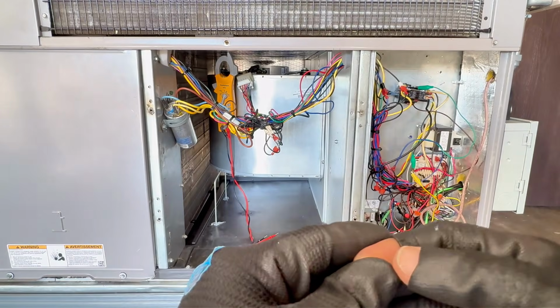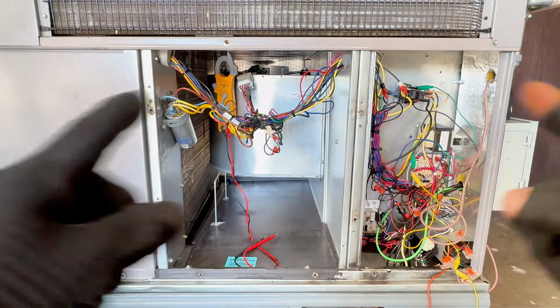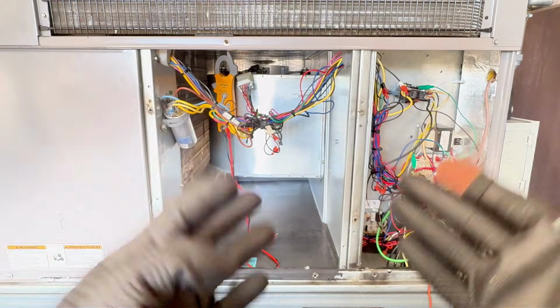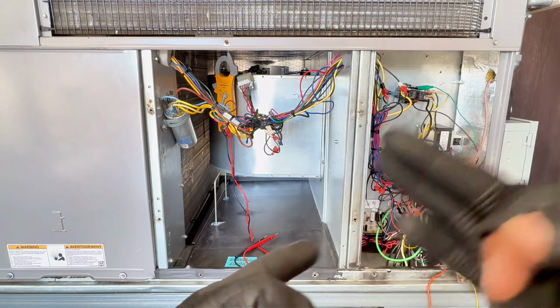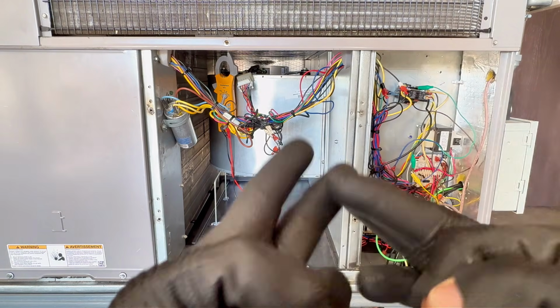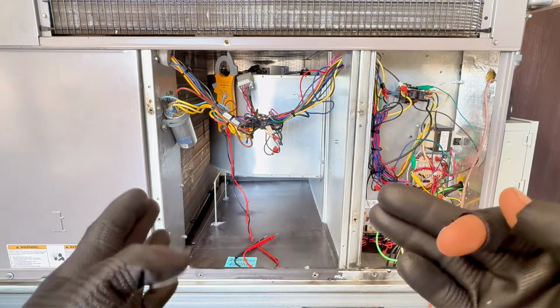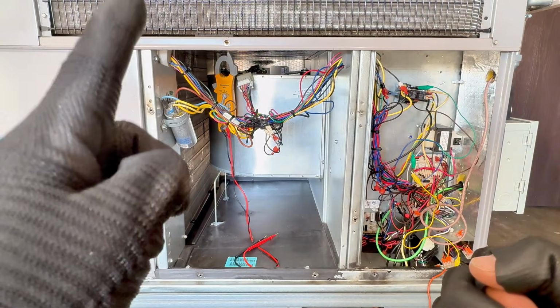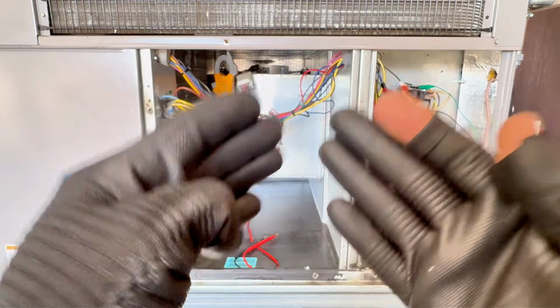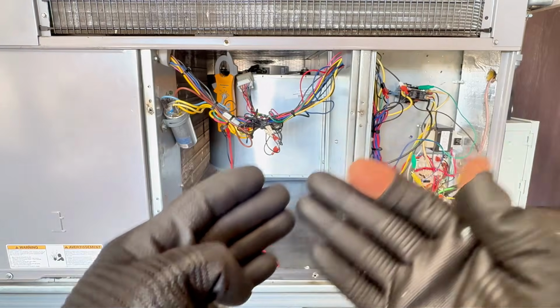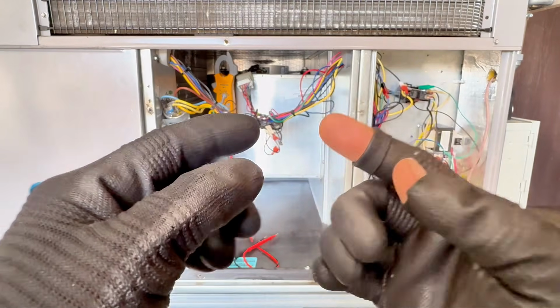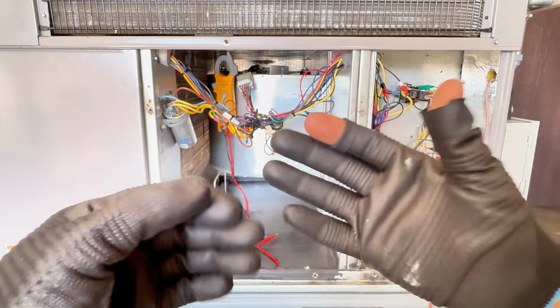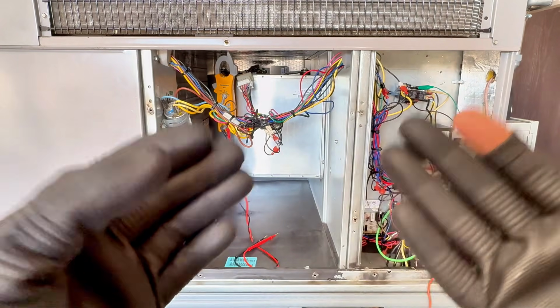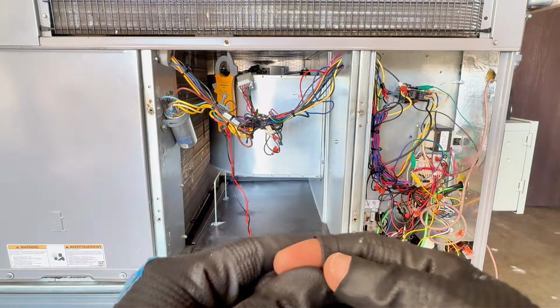So let's say you go on a service call and you're calling for cooling. In this specific package unit, this is a heat pump. So we're sending 24 volts to the contactor coil and the reversing valve. And sure enough, the compressor turns on, your condenser fan turns on, but you notice that your ECM, your indoor motor, is not spinning. The squirrel cage is not moving. You don't sense any air that's actually moving. And so how would you check if an ECM motor is working or not?